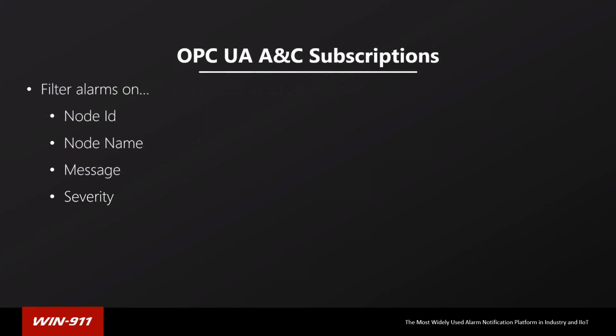For A&C, you've got one extra one. So you've got node ID, node name, which is the node ID is like the actual long syntax of a particular tag. Node name is the alarm name, and then message is like a description, and then severity is the same thing, severity. I'll show you that in a quick demo, which I'll just do right now.